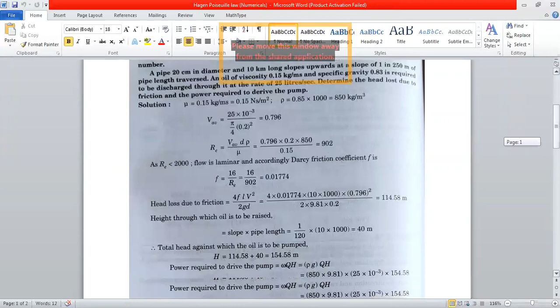So we know the power required to drive the pump is called the water power. We know that the water power is rho g Q into H. Okay, rho g Q into H. Rho is the density, so rho 850 into g equal to 9.81, Q equal to 25 into 10 to the power minus 3 meter cube per second, into total H is 154.58. So it becomes 32,224 watt, and that becomes 32.2 kilowatt. We divided by 1,000 and it comes 32.2 kilowatt.